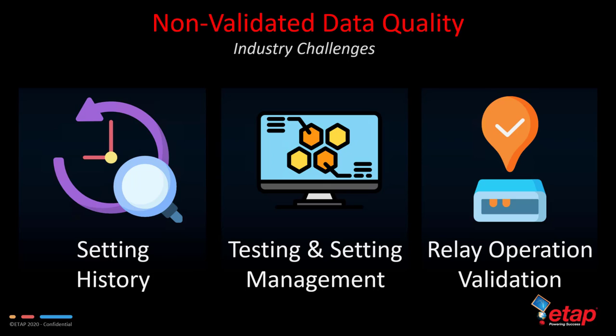Another industry challenge is non-validated data quality. There's essentially no management of the setting history based on the workflow we saw earlier. There's no formal structural relationship between the protection setting and testing management. And there's no verification and validation of relay operation with respect to the study simulation. In other words, did the relay really operate the way it was intended or designed to operate?